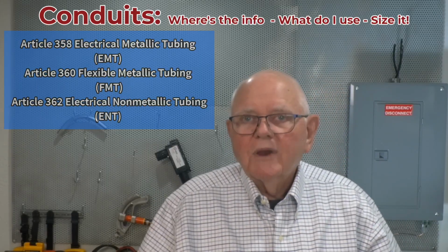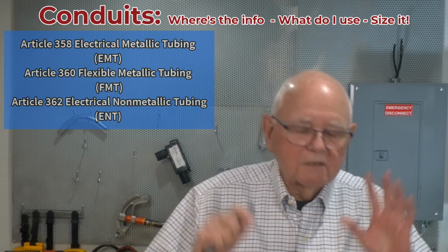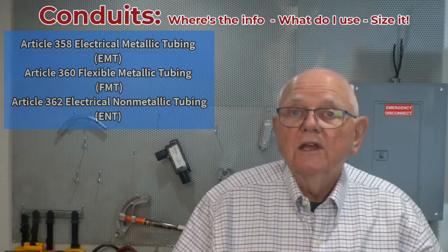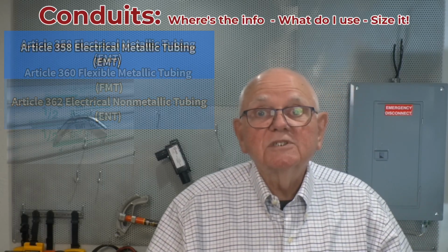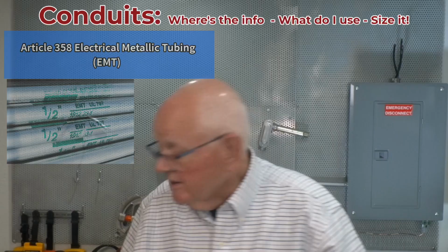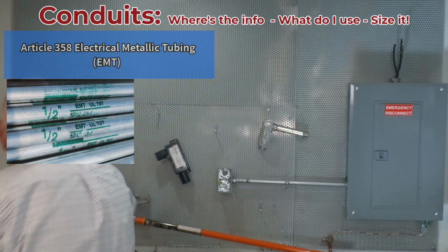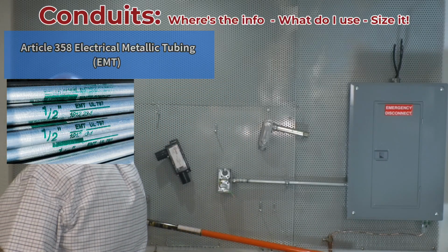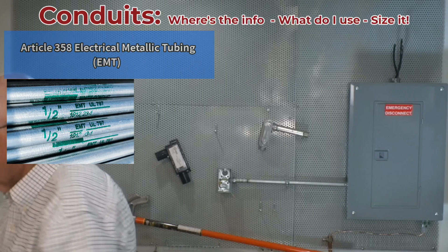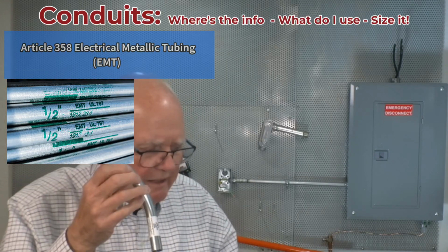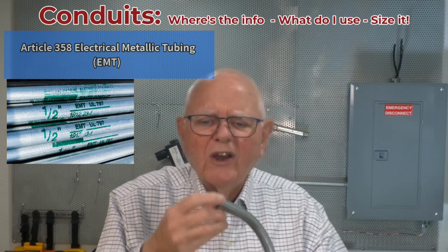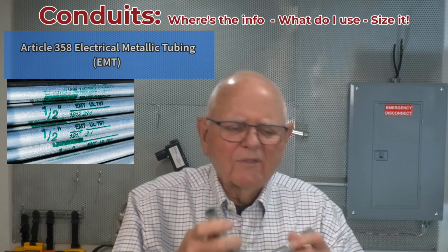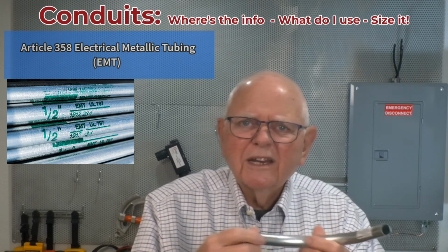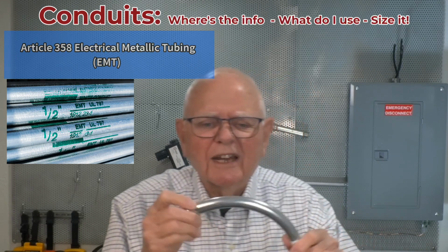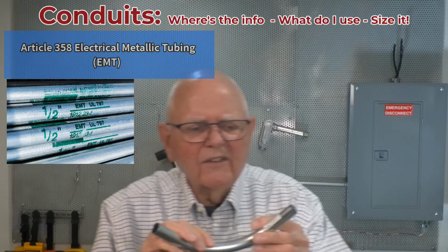Probably the first and one of the most common, certainly used all over, is thin wall, right? Electrical metallic tubing, type EMT. Now, if we look at some EMT conduit, here's another factory bent elbow. It is thin wall. I can't thread it; I'd ruin it if I tried to, right? So we're going to use either compression or set screw connectors on it to tie it all together.